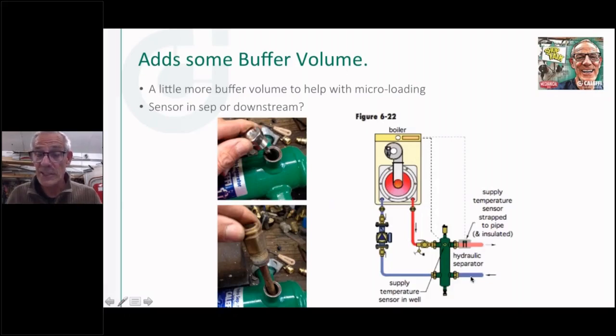If you think about this, by adding a hydraulic separator, I'm actually adding a little bit. In fact, there's probably more water in this hydro separator than there is in the heat exchanger in this boiler. So I've essentially doubled the water volume of this boiler by adding the separator to it, plus whatever fluid volume would be in the piping here. So I kind of put a mini buffer tank on this. And you can see here's exactly what I was talking about earlier, by putting the supply sensor downstream from the secondary side of the hydraulic separator.